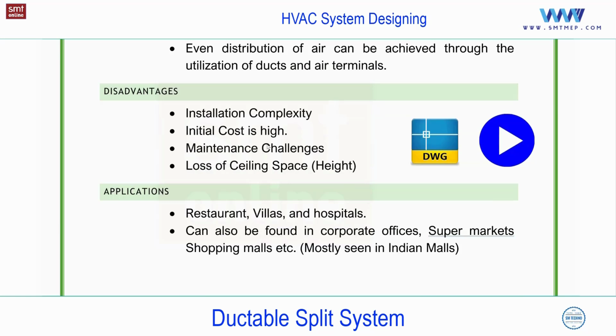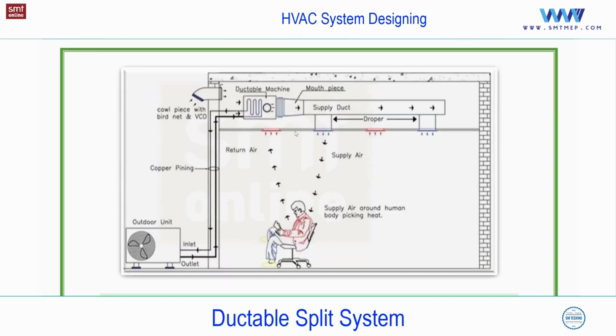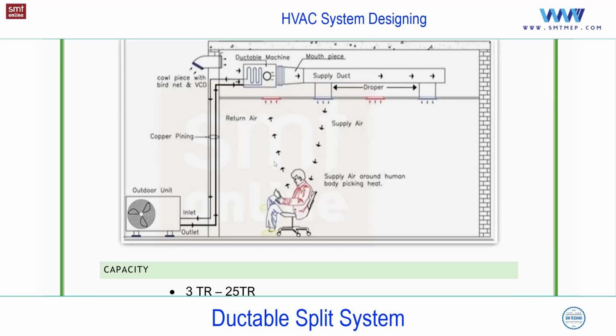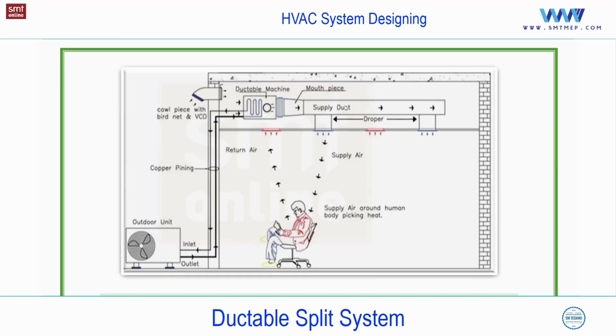Next, loss of ceiling space means in some projects you'll not find enough space above the false ceiling as per the interior requirement. So in that case, you need to compromise to maintain the height of this unit. The height of the unit is from 9 inches to 24 inches, depending on the capacity. So if it is, say, 17 TR, you need to compromise 2 feet above the false ceiling minimum. Again, above and below also some clearance is required. So you need to compromise with the false ceiling. In case of a limited false ceiling, this option is not applicable. Not only because of the unit, but because of the duct also. If you don't have enough clearance above the false ceiling, you cannot go for this ductable system. You can go with the VRF. So what is VRF? We'll discuss. Let me complete the package first.